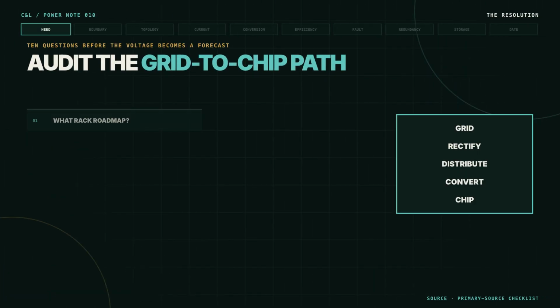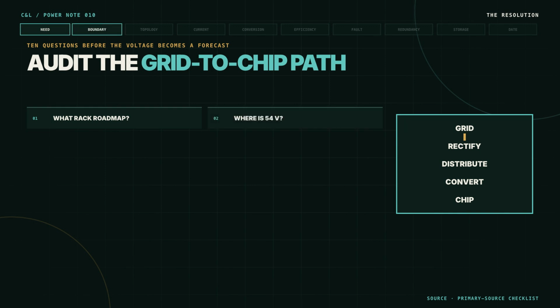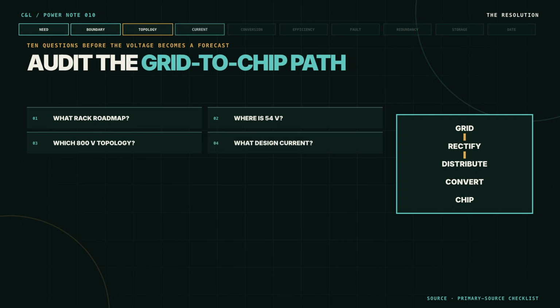Audit an 800-volt AI power proposal with 10 questions. What rack roadmap creates the need? Where is 54 volts used today, inside the rack or across the facility, is the new topology 2-conductor 800 volts or plus and minus 400 volts with a midpoint? What is the current at design load? Which conversion stages disappear, move, or remain? Where was efficiency measured and at what load?